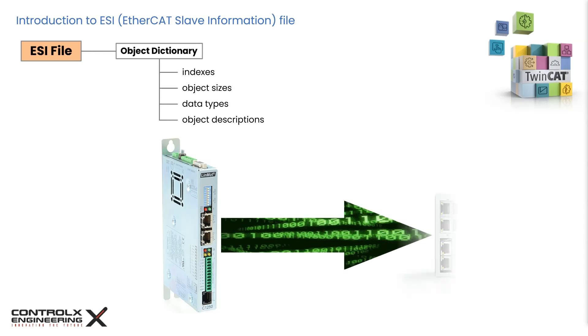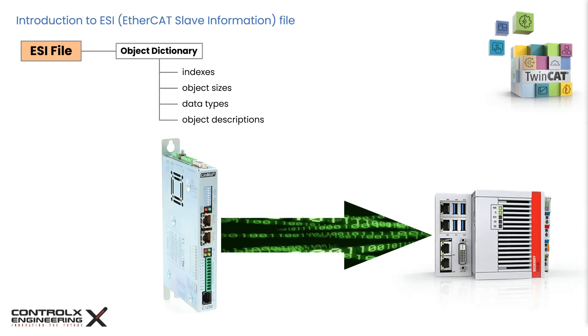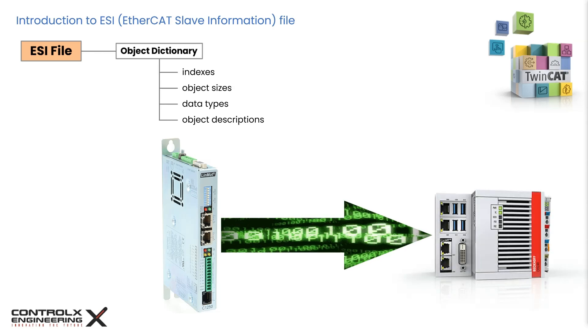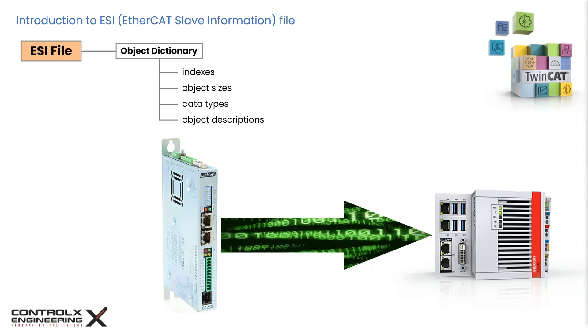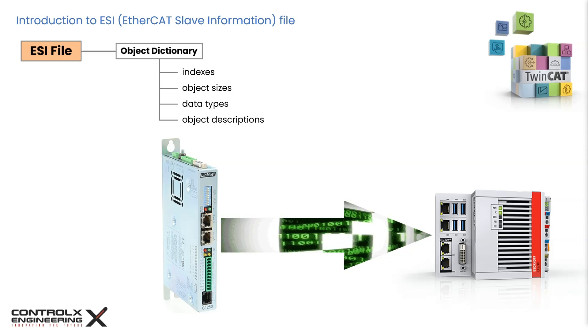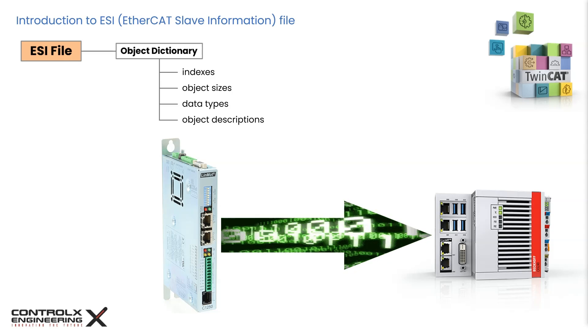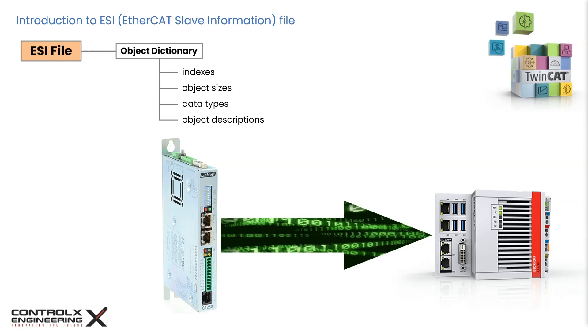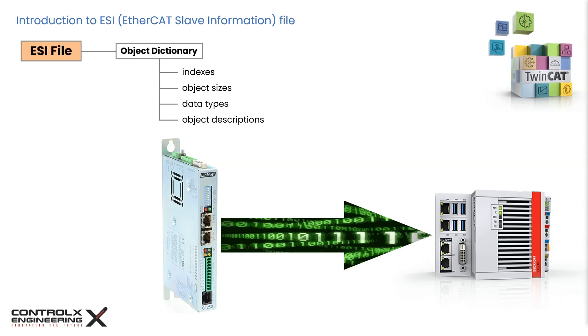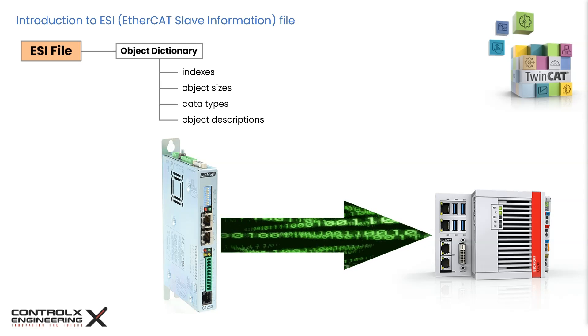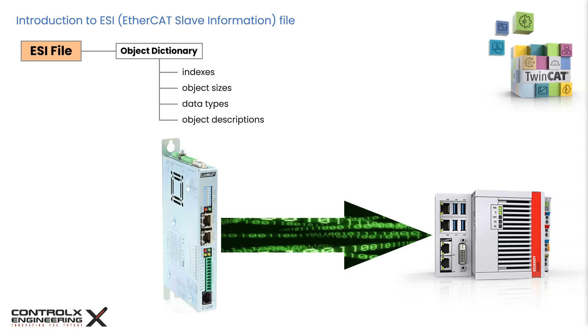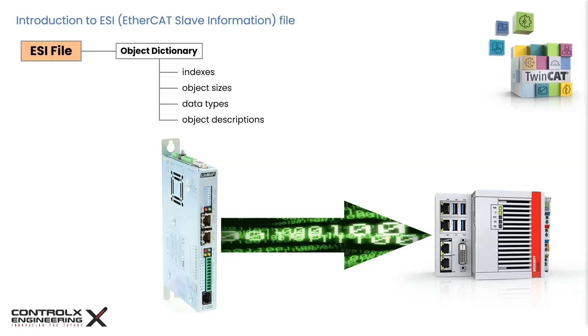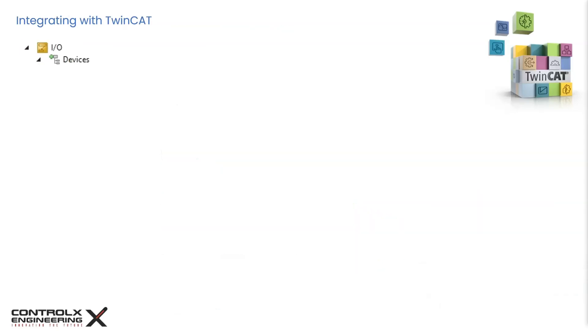The TwinCAT EtherCAT master needs the device description files for the devices to be used in order to generate the configuration in online or offline mode. The device descriptions are contained in the ESI files in XML format. These files can be requested from the device manufacturer and are made available for download. This is the IO node in TwinCAT Solution Explorer. From here we can manually add or automatically scan the physically connected hardware like IO terminals, couplers, drives, etc.